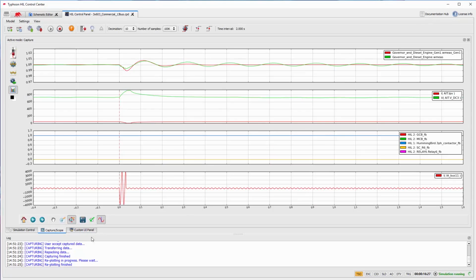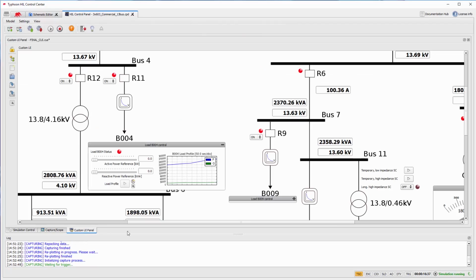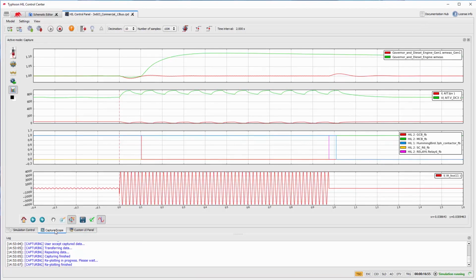The last short circuit case studied here is the high impedance permanent fault. The fault is the same as the last analyzed, but only with its duration increased. Let us enable the trigger and cause the fault. As the short circuit is permanent, the fault was cleared only by the protection relay 6 after 0.97 seconds, confirming that the relay is operating as desired.